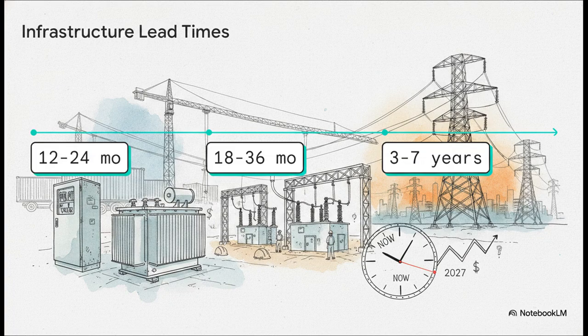You can't just order a power plant on Amazon with next-day delivery. The electrical grid infrastructure required to deliver hundreds of megawatts doesn't just magically appear. Medium-voltage switchgear and transformers have lead times of 12 to 24 months. Utility-grade substations take 18 to 36 months to design, permit, and build. And if you need high-voltage transmission line upgrades, you're looking at 3 to 7 years.